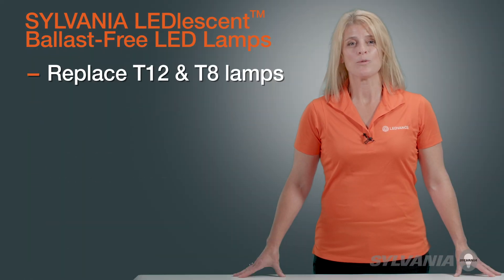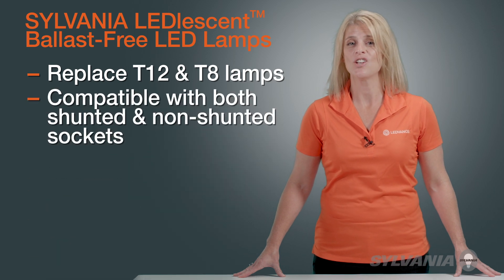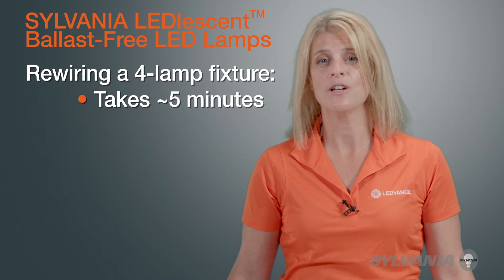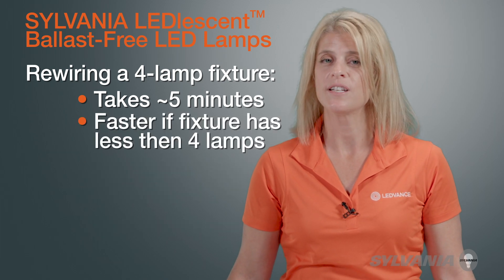Sylvania LEDlescent lamps replace T12 and T8 bi-pin fluorescent lamps. They are compatible with both shunted and non-shunted sockets. Rewiring an existing four-lamp fluorescent fixture can be accomplished in place in about five minutes. If the fixture has less than four lamps, the retrofit is even faster.